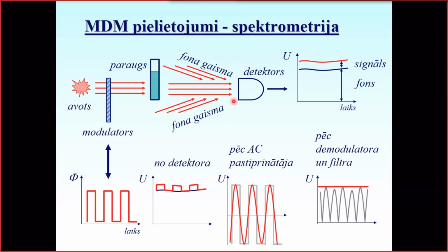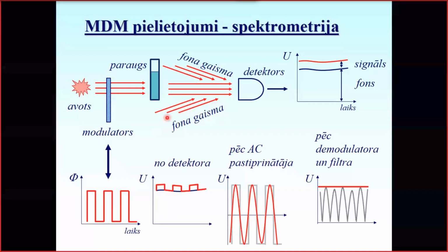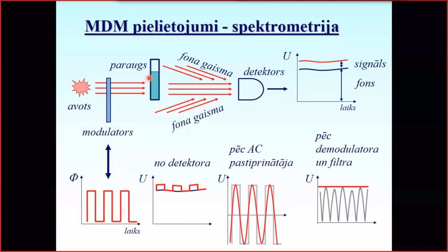But if it didn't isolate all the measurement chamber completely from the stray light, we get some kind of ground light, so-called stray light. So it comes even, especially if you're going to provide some chemical reaction in the cuvette, in the specimen cuvette, and have to put some kind of tubing inside. And for this, we actually have to open a little bit this chamber.